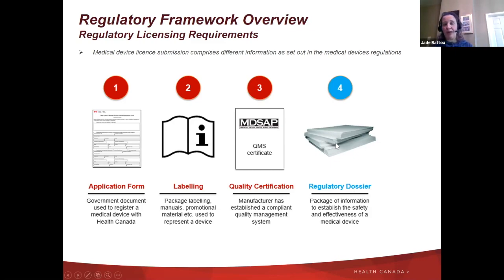In addition to that, for class 3 and 4, and even 2, they have to supply what we call a regulatory dossier, where we can find the scientific information about the device itself - any testing, any clinical research data, any marketing information in other regulatory jurisdictions. We ask for this regulatory dossier for class 3 and 4 medical device license applications, not for class 2. For class 2, the manufacturer has to have the regulatory dossier, but they don't have to submit it to Health Canada unless it's requested.